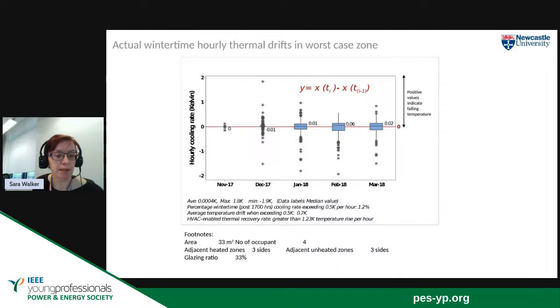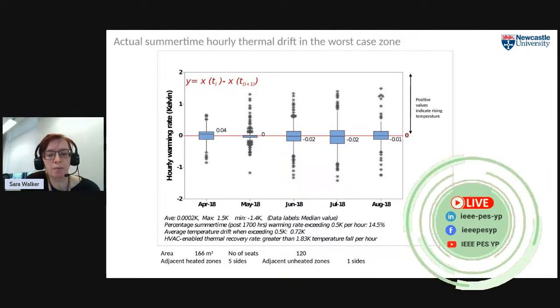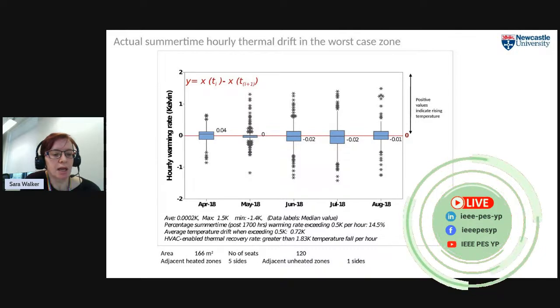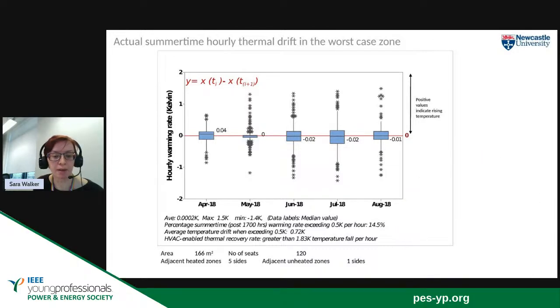Now, this is a commercial building, and like many other commercial buildings, it's got a cooling load, not just a heating load. And so we looked at the performance of the heat pumps in reverse, offering cooling to the space, and what happens if we turn the cooling off. When we looked at summertime and at the drift in temperature and how quickly the building warmed up, we found that the building did warm up quicker than it cooled down. In summertime, we saw a temperature increase of 0.5 degree per hour happening about 14.5% of the time in these summer months that we looked at when there was cooling demand.